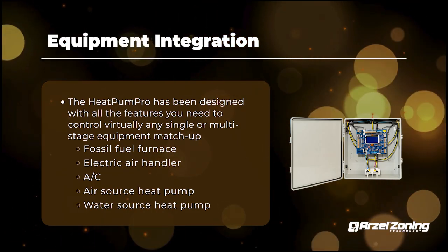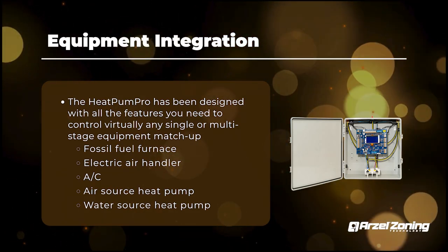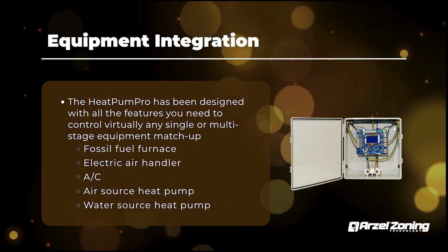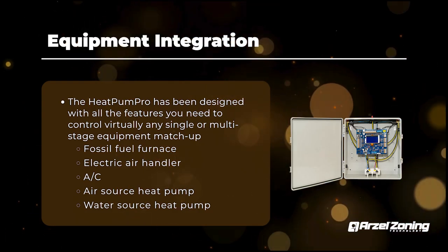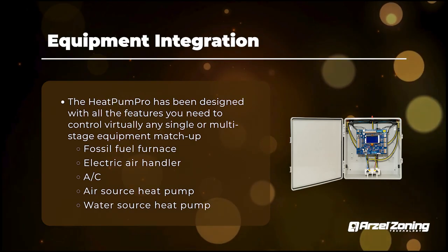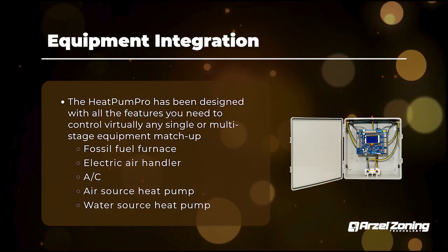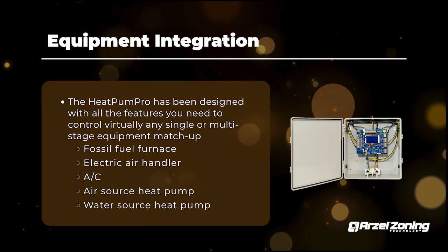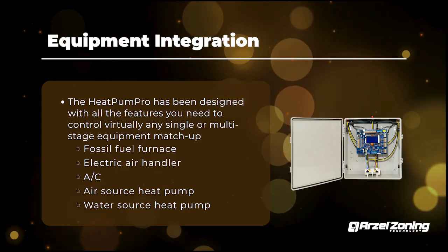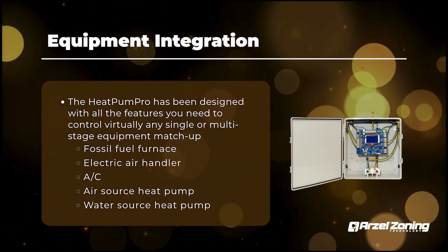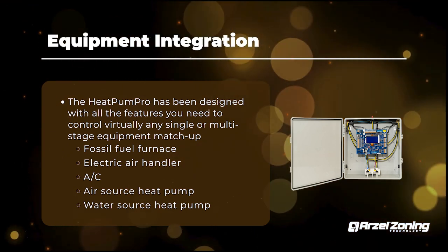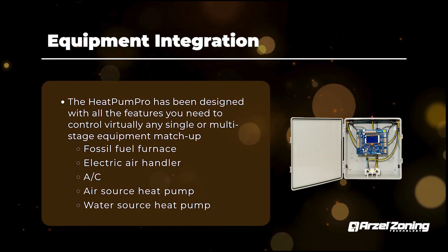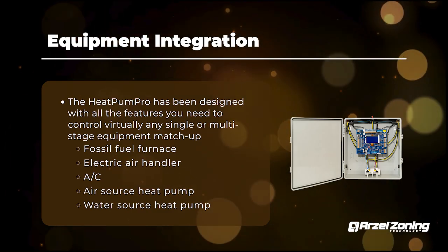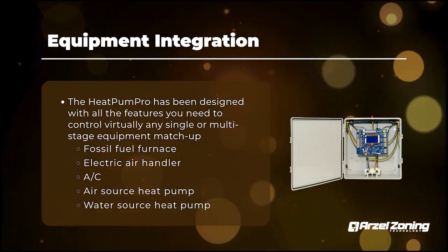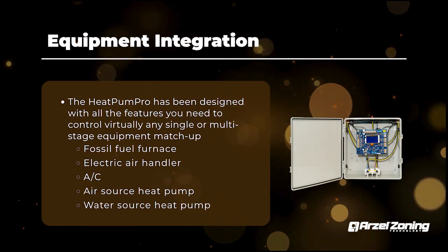If you ever have a need for more than 35 dampers, we can build a custom panel. It essentially has 2 pumps built into the bottom of the panel box, and then we can do up to 70 dampers. Just keep in mind when you're counting the dampers, some of your larger size dampers have 2 actuators on them, so 2 of the heads where you connect your air lines, and each one of those is considered a damper. So if you have 2 heads on a bigger damper, that's going to be 2 dampers essentially. You've got to keep that in mind. It's per actuation head, and that's how we get that number.